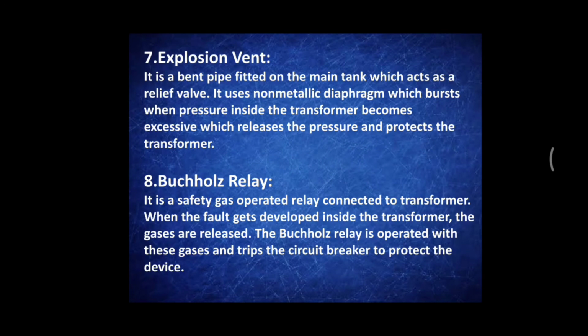Seventh, explosion vent. It is a bent pipe fitted on the main tank which acts as a relief valve. It uses a non-metallic diaphragm which bursts when the pressure inside the transformer becomes excessive, which releases the pressure and protects the transformer.